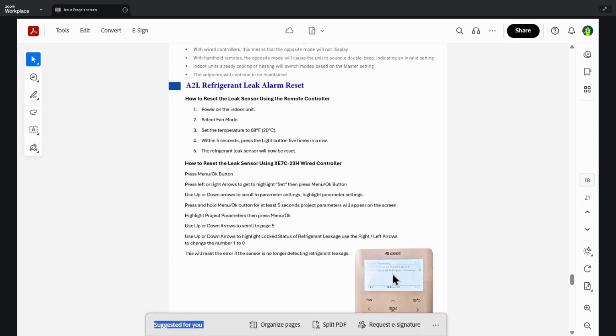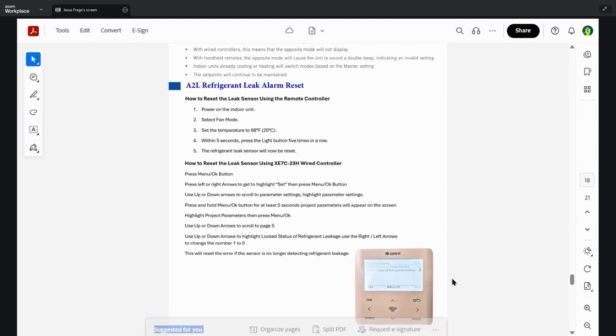So pretty much you have to go through the parameter settings and actually physically change the locked status of the refrigerant leakage. So what that means is you have to go in and change 1 to 0 to be able to do the reset of the refrigerant leak sensor.